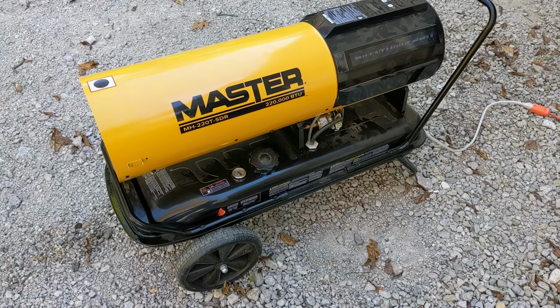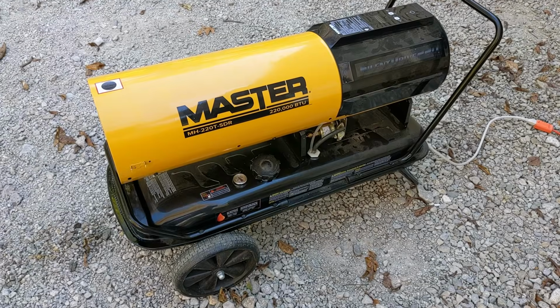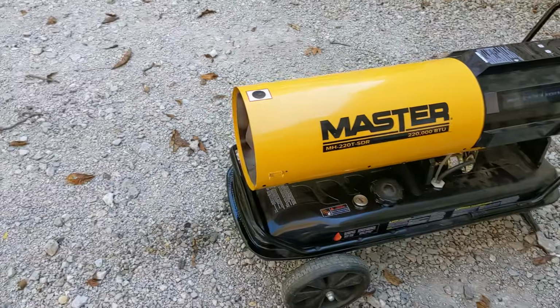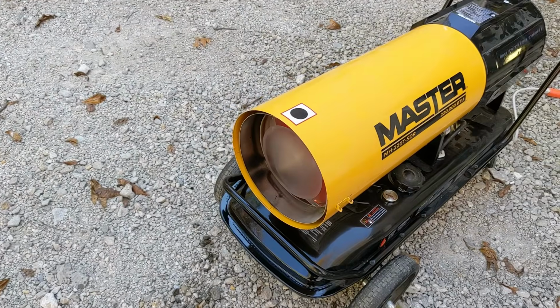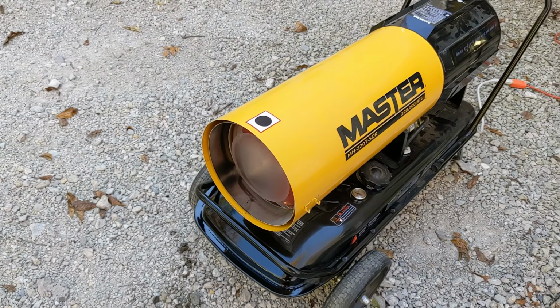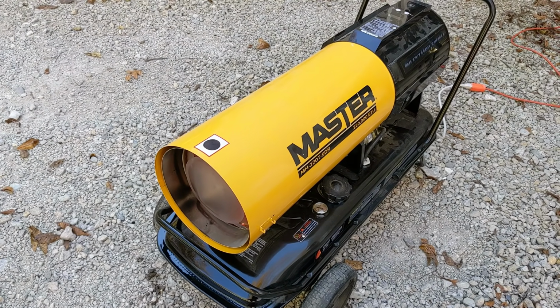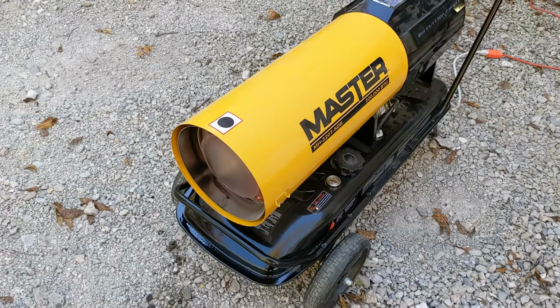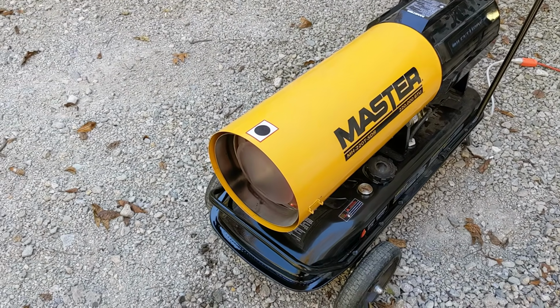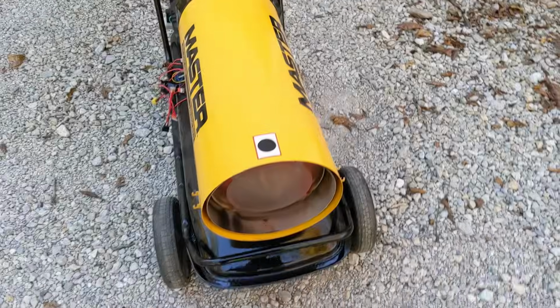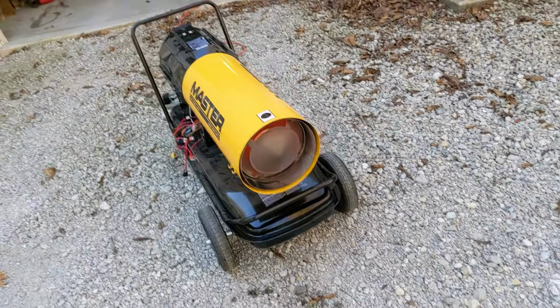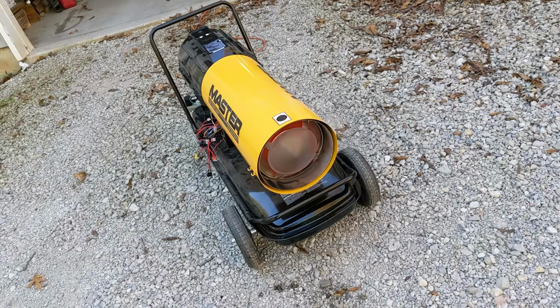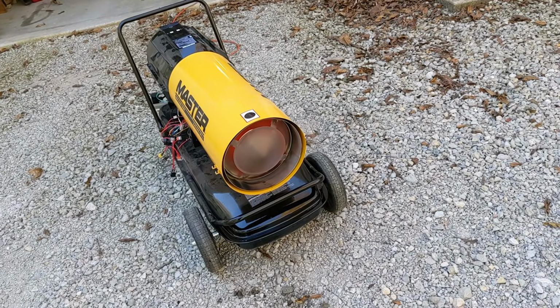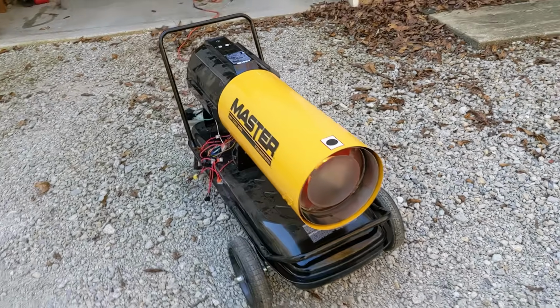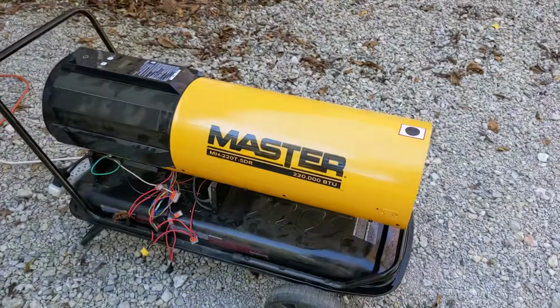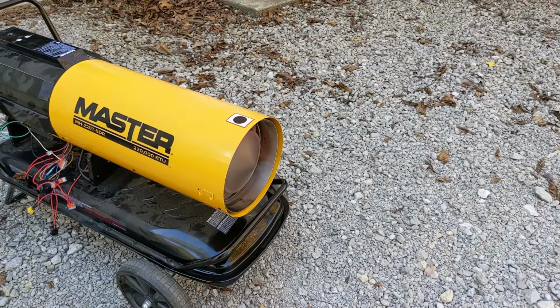So I think I've been proven right that the problem was the electronics. There's nothing wrong with this machine. Obviously the filter's not clogged, the igniter works, the fan works, the thermal overload circuit is still in there. I tested the photo cells and they tested good on the bench. The board should have been getting a signal that yes, I see ignition in the chamber. So the electronics were the problem with this machine, because mechanically everything runs like it should.